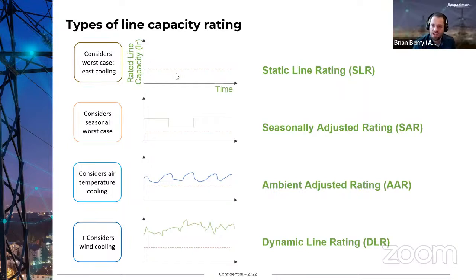Basically what that's saying is we're going to assume it's the hottest day, very hot temperature, no wind, nothing else cooling the line. If you were to run it like that, this is how hot it would get, and then it would be damaged. So that gives you X amount of amps you can push through the line.